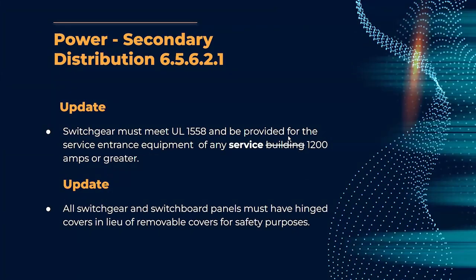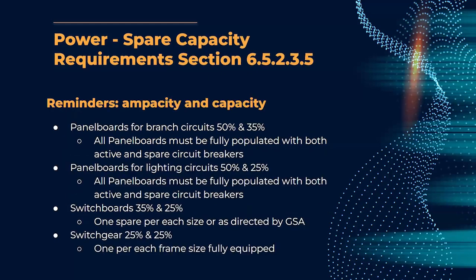So moving into power. This first bullet here is not new to P100, but we have rewritten this section a few times to try to capture our intent. So we do require draw-out switchgear, UL 1558, for any service that's 1200 amps or greater. Switchboards, UL 891, can be used for under 1200 amps. The second bullet is brand new to P100: all switchgear and switchboard panels must have hinged covers in lieu of removable covers for safety purposes.